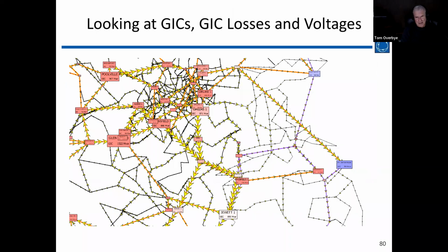Here's again at 28 seconds, I restored the power flow, and I'm visualizing with the yellow arrows how the GICs are flowing through the system. The rectangles are geographic data views where the size of the rectangle is proportional to how much reactive power is being lost at that bus due to the GICs, and the color is the voltage level. This is kind of the Dallas area, so it's kind of ground zero, so there's a lot of GIC losses there and a lot of depressed voltages.